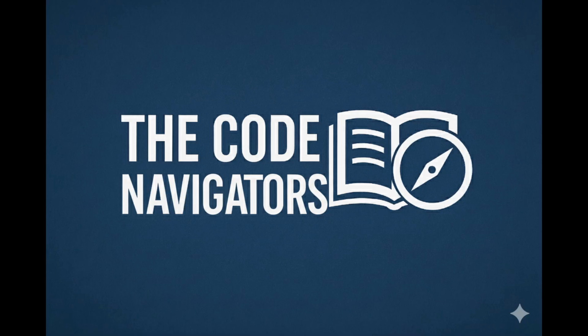They do. And 1008.3.4 specifies for how long. The emergency power has to keep those lights on for at least 90 minutes. Why 90 minutes specifically? It's calculated to be long enough for everyone to get out, and then for the fire department to arrive and begin search and rescue operations in what might be a dark, smoky building. It's a margin of safety for the first responders.